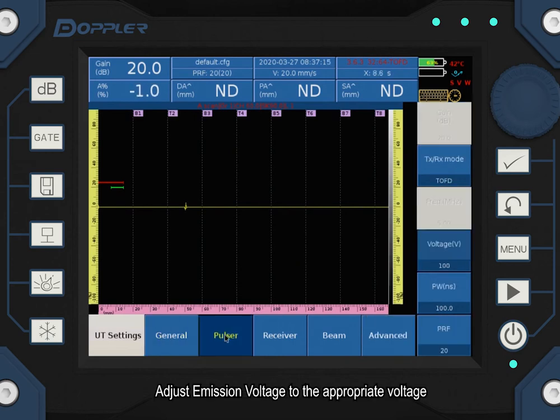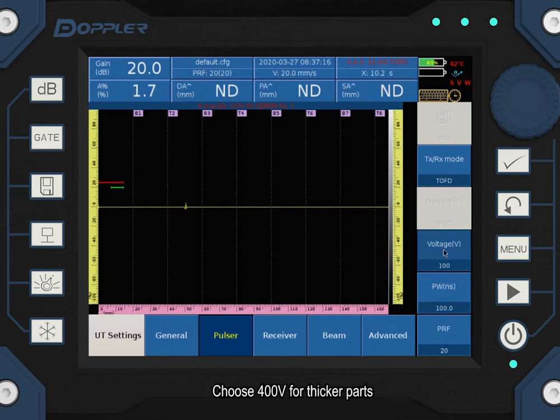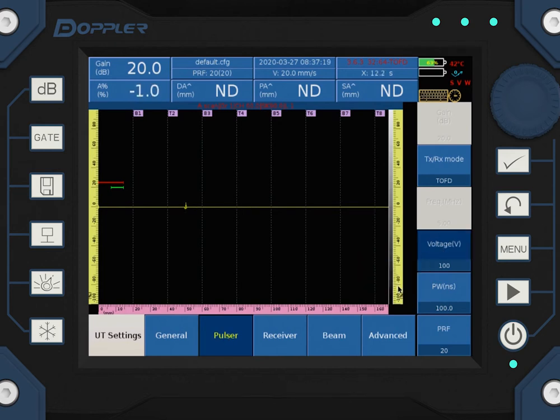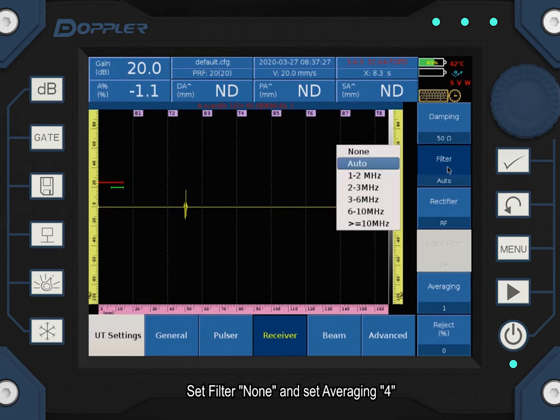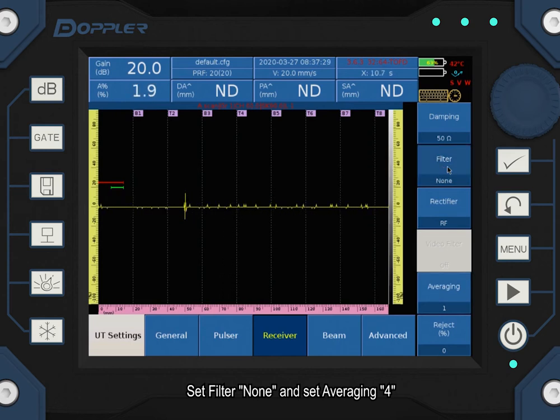Adjust emission voltage to the appropriate voltage. Choose 400V for thicker parts. Set filter to none and set averaging to 4.